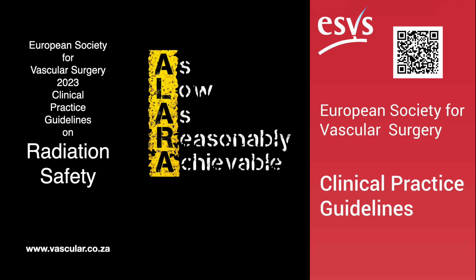This is another really important concept to grasp. Conventional magnification on most C-arms works by electronically selecting a smaller area of the detector to display over the full monitor screen. So you zoom in by using less of the detector. Exactly. This increases spatial resolution, letting you see finer details, but there's a significant dose penalty.